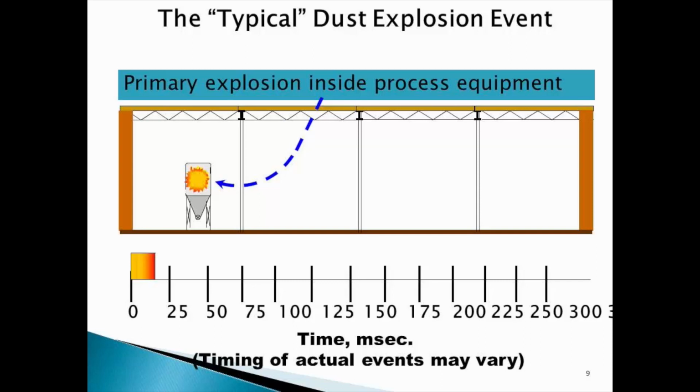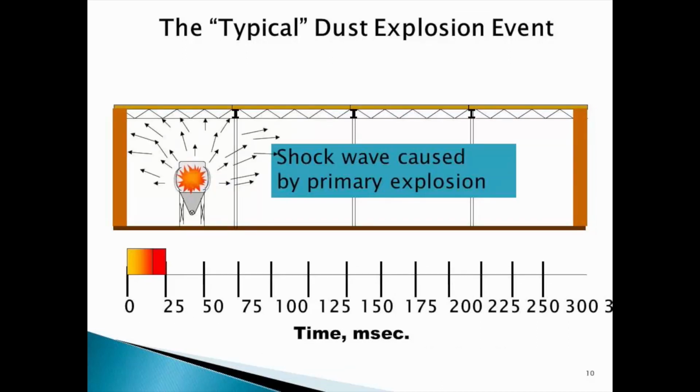As mentioned earlier, in order for an explosive dust cloud to be formed, the dust must be exposed to a process that suspends the particles in the air to the extent that the dust concentration rises into the explosive range. Most often such dispersion of dust to form explosive clouds takes place intentionally inside process equipment, as shown in the figure. After the explosion, the shock wave can damage and rupture the walls, allowing the burning dust and gases from the explosion to be expelled into the surrounding area.